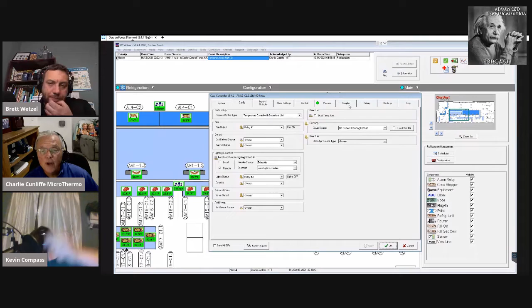If you see a graph that's all kinds of spiky, then you haven't done your job. So you should see your peak up like this on defrost, and once I go back into refrigeration, it should drop like a rock, and that's the way it should run. Totally linear, right on top of your set point. And the more linear you get all those graphs, the better off all the rest of the graphs are going to be as far as all your pressures and stuff.